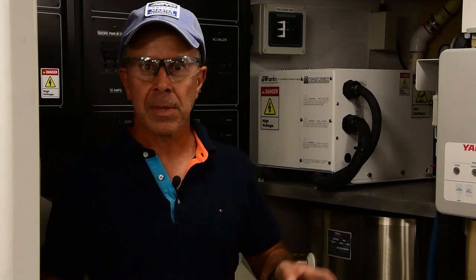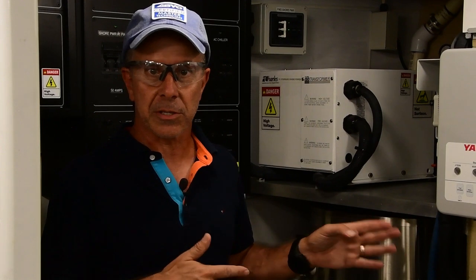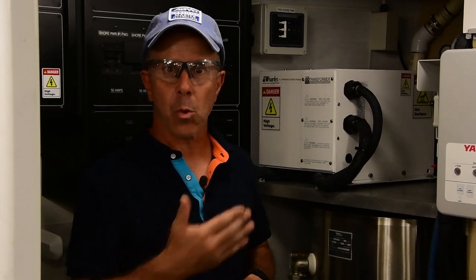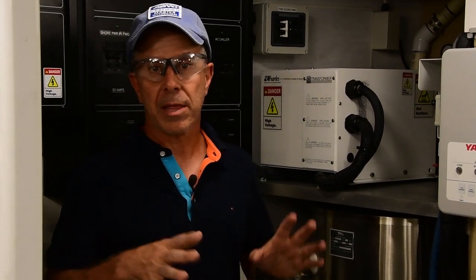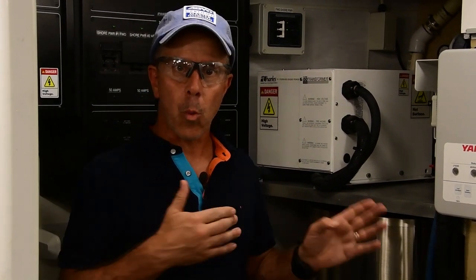You're both plugged into ground, so you're common. Your zincs could be protecting the boat next to you. The transformer prevents that because there's no connection between your boat's ground and the dock ground once a transformer is installed. That is only the case with an isolation transformer. Now, if you wire this as a polarization transformer, you don't have the benefit of that isolation.